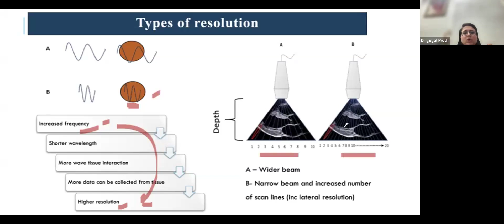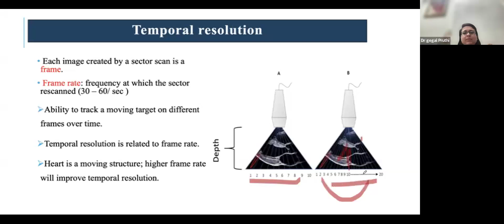Now, what is temporal resolution? Temporal resolution is the ability to display rapidly moving structures and distinguish closely spaced events in time. Hence, it is closely related to the frame rate. Now, temporal and lateral resolution are not friends. As we have seen in figure B, which has 20 scan lines, there it was having more lateral resolution. But as temporal and lateral resolution are not friends, when you have more number of beams coming up and down, it will take longer time to finish one sector and then to start a new frame. So anything that requires more time, like the deeper sectors, the lesser is the temporal resolution.